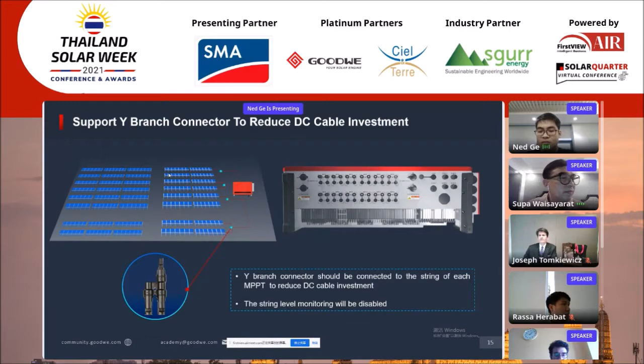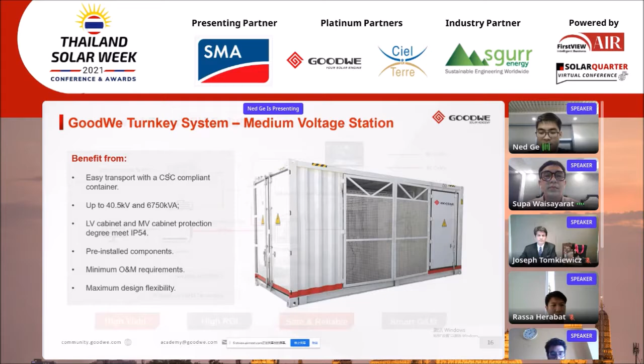Well, the next product we are releasing to the market is the GoodWe medium voltage container type power station. The medium voltage power station offers very high power density in a plug and play design, and the maximum capacity is now up to 6,800 kVA, suitable for global use. This turnkey system generally has main components including the medium voltage switchgear, the transformer, the low voltage switchgear, and even the bus duct, internal connection cable and the auxiliary circuits in it. The pre-assembled 20-foot container is assembled at the factory and shipped in one piece, so it is simple to drop in place and connect cables. So site work will be less, and all the equipment conforms to Thailand local regulations.